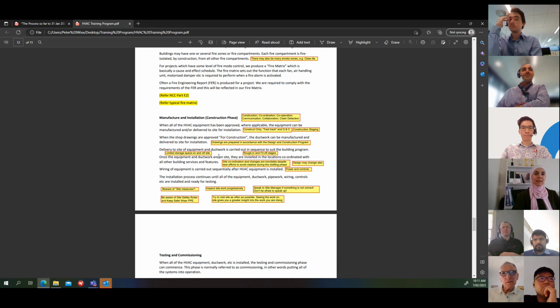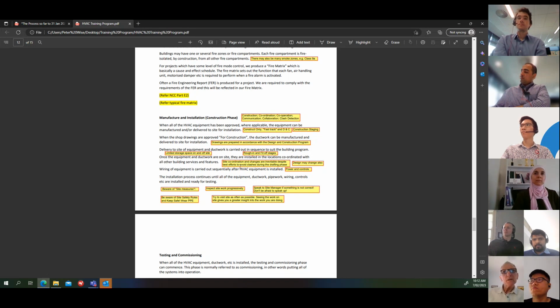For the smaller projects, most of the ductwork, pipe work, and equipment is in the ceiling space. They'll want to put their ceilings in as soon as they can. So you've got to make sure that everything's in the ceiling before they build the ceilings, because otherwise they'll be pulling ceilings down and somebody's got to pay for that. So it's about being aware of the program, and going back to these C's: communication, coordination - all of these things are really important. Keep talking to the builder, understand what the program is, make sure that you get things done on time.